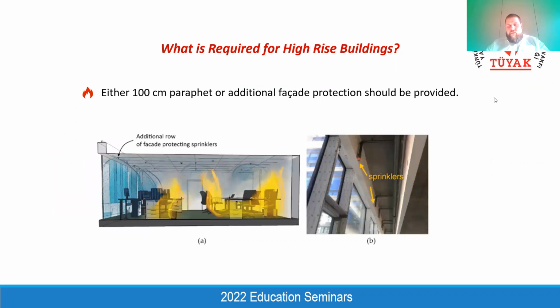And also, this is a very important issue. This is specific to Turkish fire code. If we don't have a 100 centimeter height, 2-hour fire rated parapet on the facade between the floors, the Turkish fire code requires closely located sprinkler heads for the facade protection. For the curtain walls, in Turkish it's called giydirme cephe. If you have a glazing facade for your building, it is really hard to provide these 100 centimeter spandrel panels on the facade because it really affects the outer look of your building negatively.